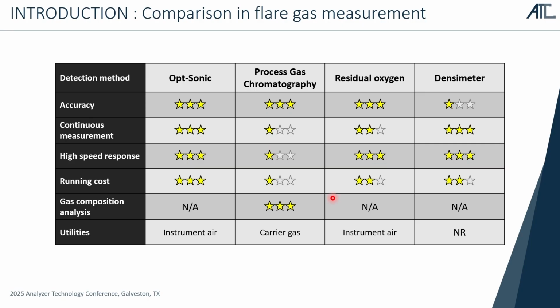And the running cost: the optosonic sensor doesn't have any consumables, so the customer doesn't need to replace consumables. So the running cost is good. The weak point of this sensor is gas composition analysis. It's not available with this sensor technology, just BTU monitoring. And as for other required utilities, instrument air or nitrogen is required. And next is the gas chromatograph, GC.